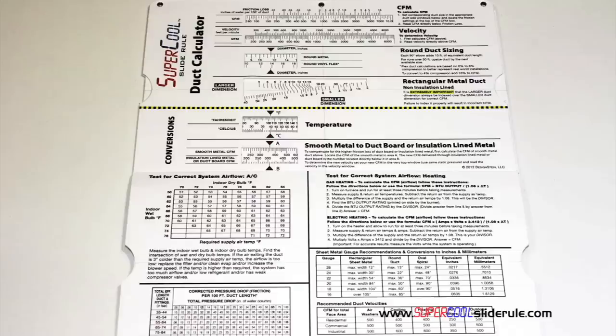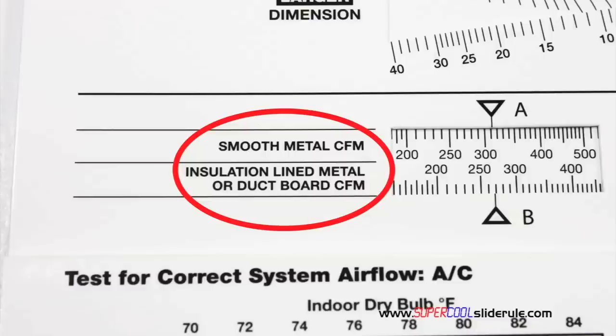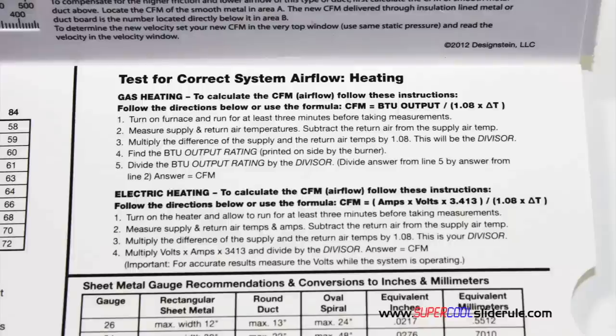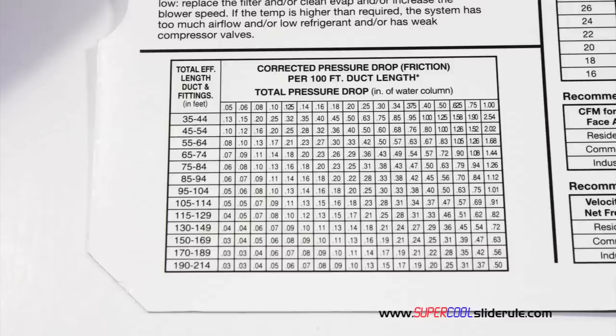Inside is packed with even more information. It performs sizing of both metal and flexible duct. It has the only direct reading conversion from smooth metal to insulation lined metal we've ever seen. The majority of technicians have never been taught that if the insulation is on the inside of the ductwork, you cannot size it with a regular duct calculator. It has step-by-step directions for determining airflow through a gas furnace, electric furnace, or an air conditioning unit. It has pressure drop multipliers for ductwork as well as recommended velocities.